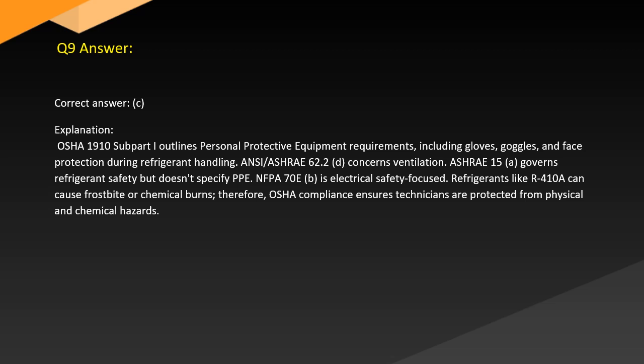Answer. Correct answer: C. Explanation. OSHA 1910 Subpart I outlines personal protective equipment requirements, including gloves, goggles, and face protection during refrigerant handling, and ASHRAE 62.2 (D) concerns ventilation. ASHRAE 15 (A) governs refrigerant safety but doesn't specify PPE. NFPA 70E (B) is electrical safety focused. Refrigerants like R-410A can cause frostbite or chemical burns. Therefore, OSHA compliance ensures technicians are protected from physical and chemical hazards.